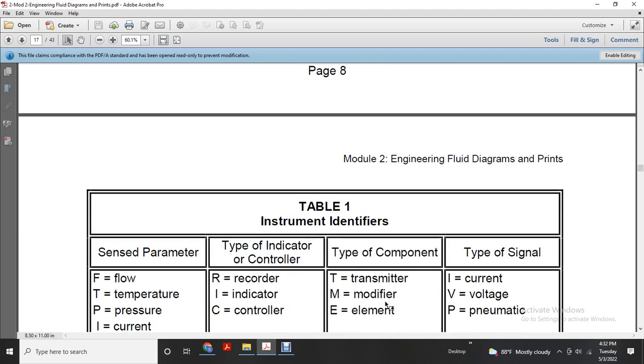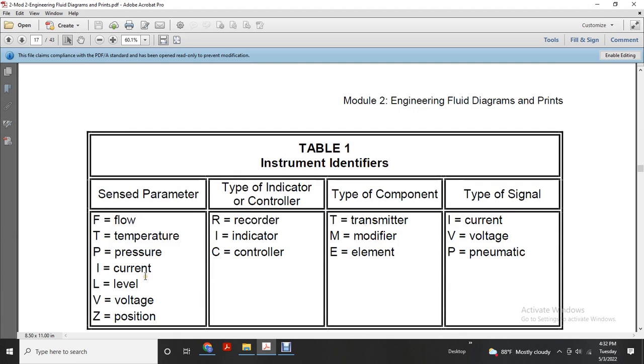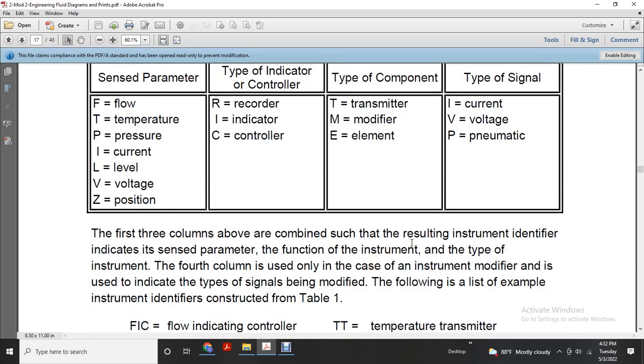Alright, Table 1: the instrument identifier, with the sensed parameters F for flow, T for temperature, P for pressure, I for current, L for level, V for voltage, Z for position. The type of function: I for indicator, R for recorder, C for control. The type of component: T for transmitter, M for modifier, E for element. The type of signal: I for current, V for voltage, P for pneumatic. These first three columns are combined to identify the instrument with the sensed parameter, the function, and the type of the instrument.